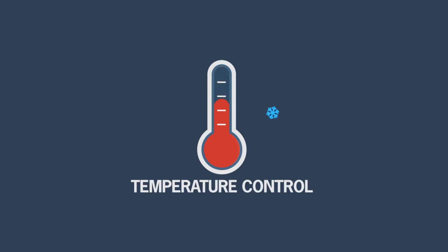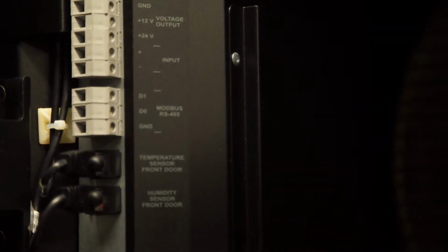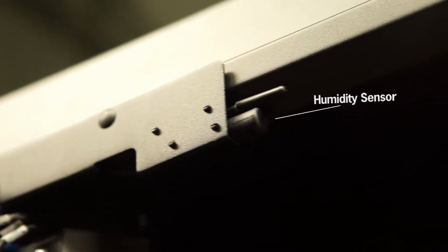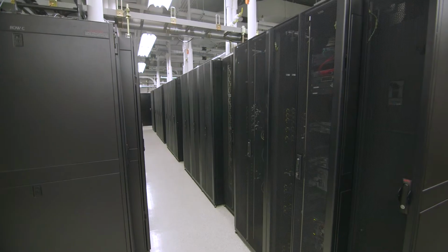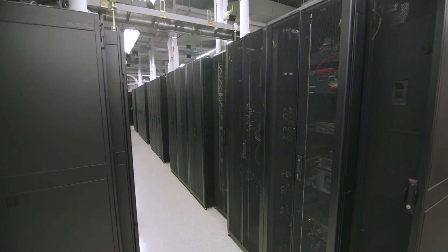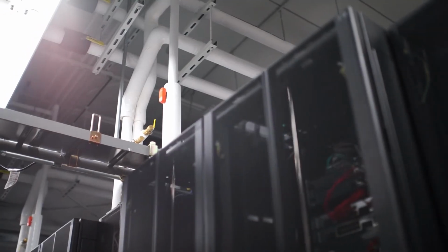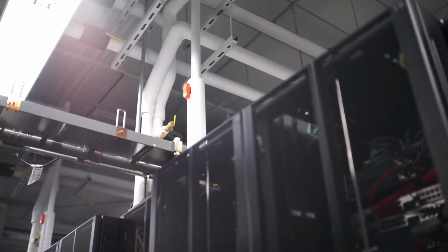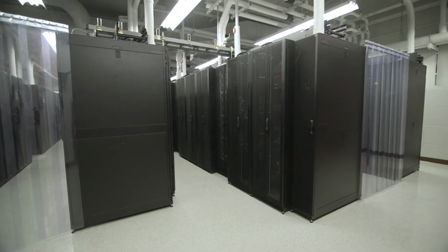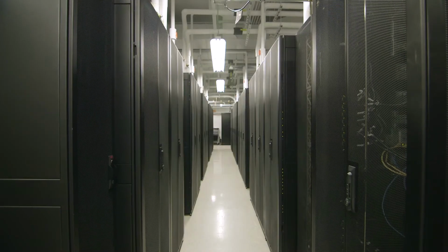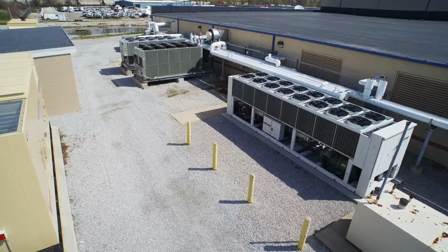Speaking of the environment, we're also very conscientious about temperature and humidity levels, monitoring them closely to both prevent static discharge or condensation that can lead to corrosion, electrical malfunctions, and damaged equipment. Here, you'll see rows of APC cabinets with inline chillers built into the rows of cabinets. They've been set up with a hot aisle and a cold aisle configuration. This allows the room to maintain consistent temperatures for optimum effectiveness.